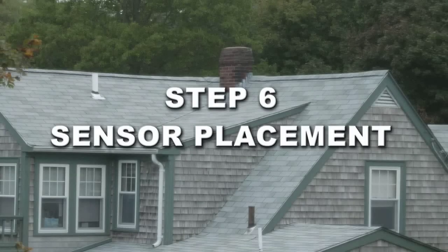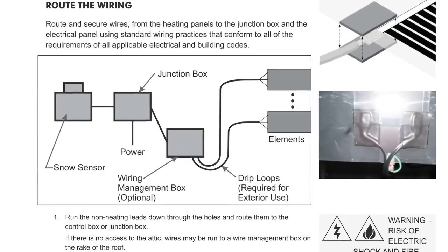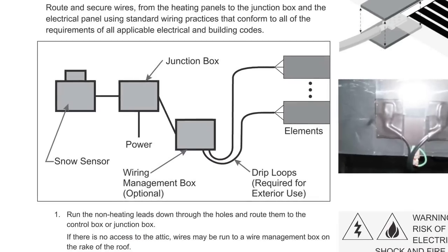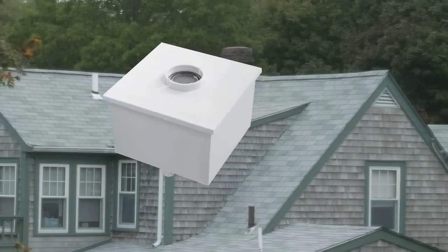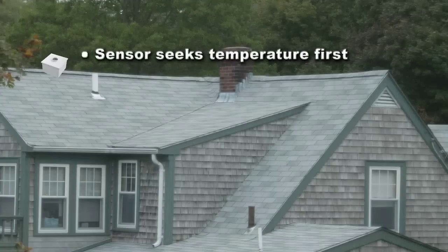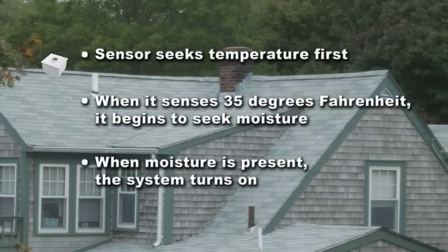Step 6: Sensor Placement. The Calorique Roof De-Icing System utilizes a two-stage sensor. To ensure optimum function, the sensor should not be obstructed from weather conditions. Therefore, it must be mounted at the highest possible point on the roof. The sensor seeks temperature first. When it senses 35 degrees Fahrenheit, it begins to seek moisture. When moisture is present, the system turns on.